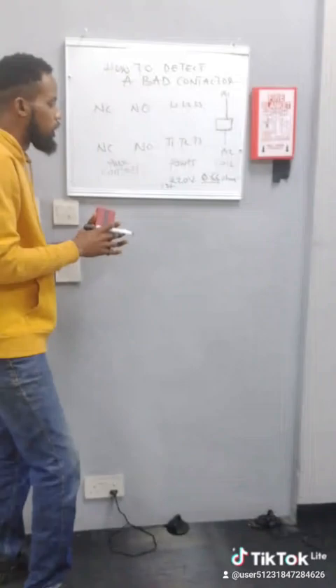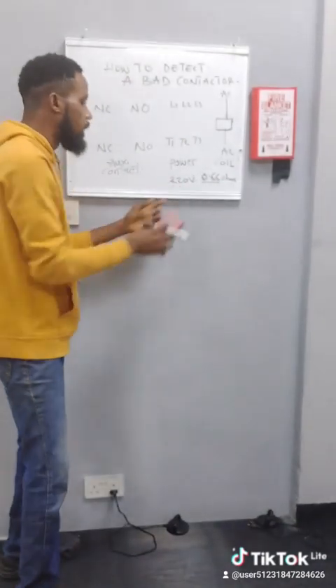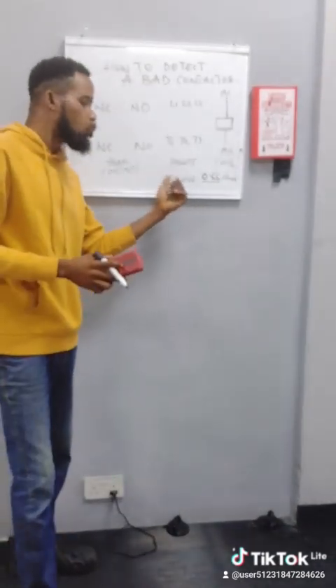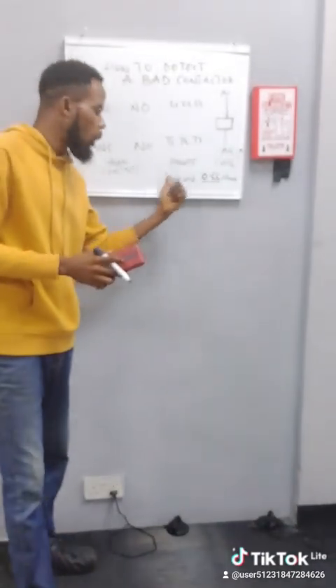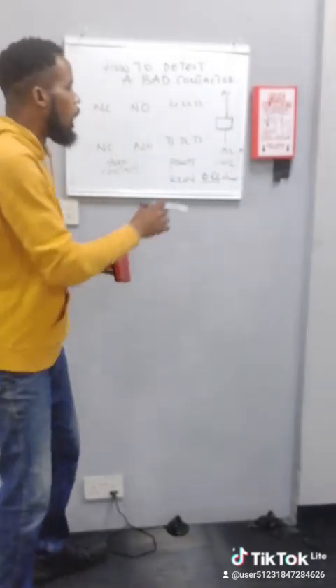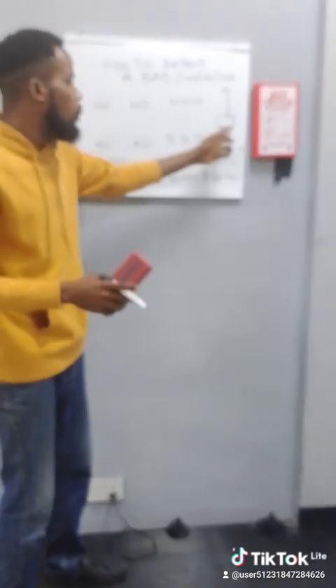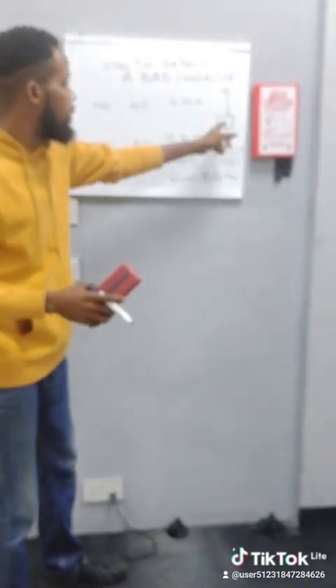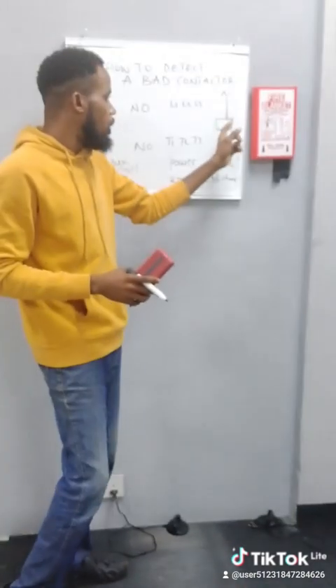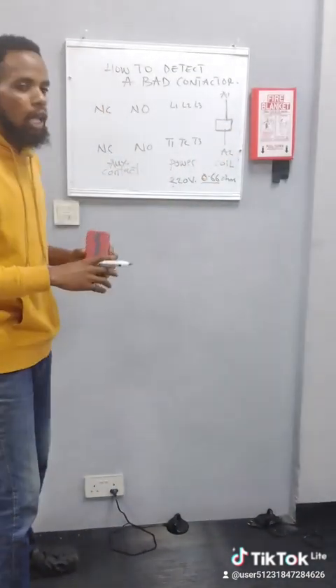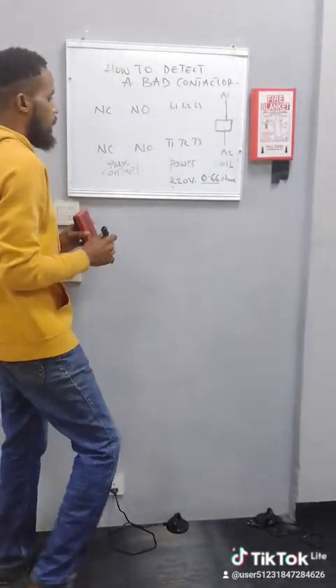So you need to check the voltage. If it's not 200 to 220 volts, that means the voltage will not be able to energize the coil in the contactor.